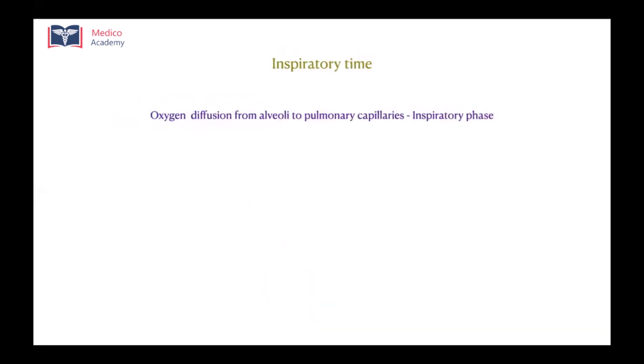So the next is inspiratory time. Usually most of the ventilators will have a setting for inspiratory time. As we discussed earlier, the oxygen diffusion from alveoli to the pulmonary capillaries usually occurs during the inspiratory phase. So the inspiratory time ideally has to be adjusted between 1 and 1.5 seconds. So what happens if you set an inspiratory time of more than 1.5 seconds?